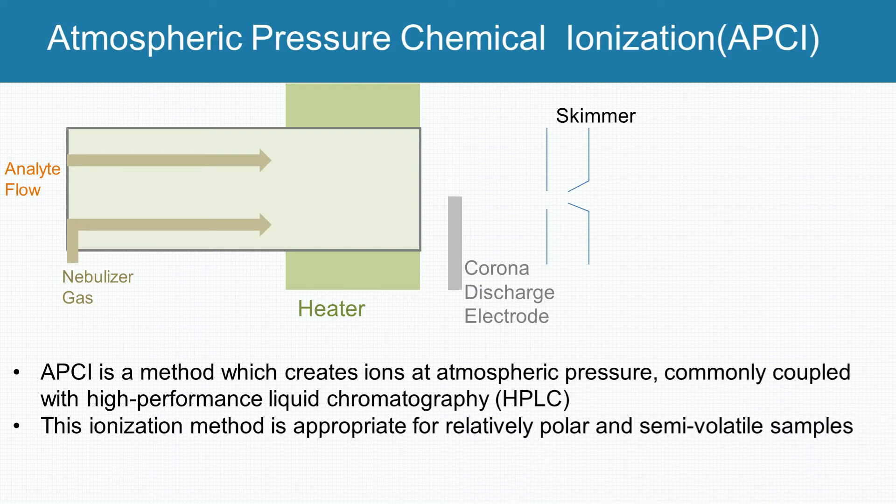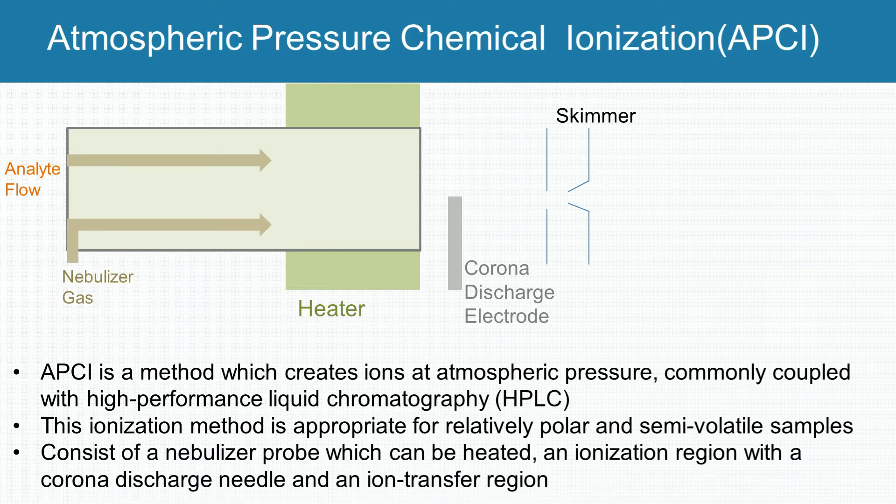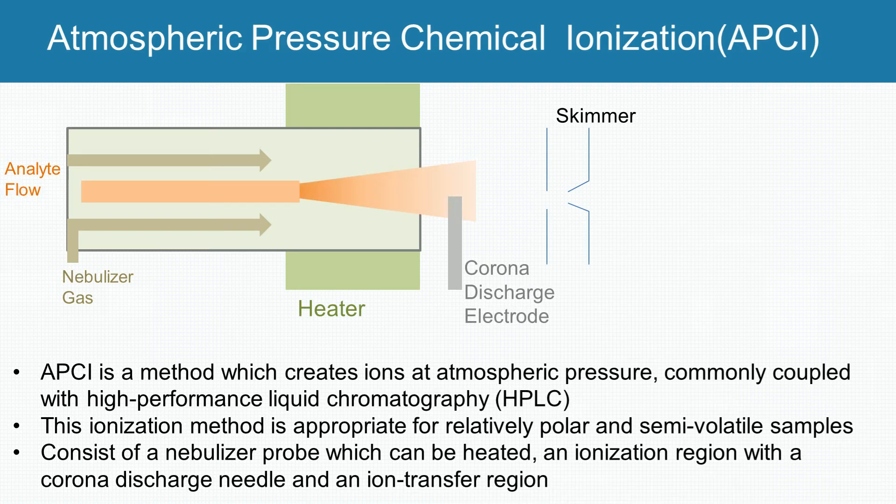An atmospheric pressure chemical ionization system consists of a nebulizer probe, which can be heated, an ionization region with a corona discharge needle, and an ion transfer region. A sample solution flows through a heated nebulizer where it is produced into a mist and the mist is transformed into a gas stream. When the gas stream arrives in the ionization region at atmospheric pressure, the gaseous solvent and sample are then ionized by a corona discharge.